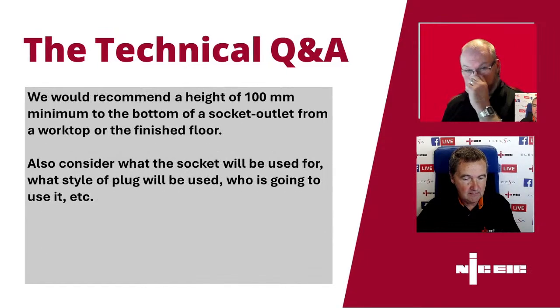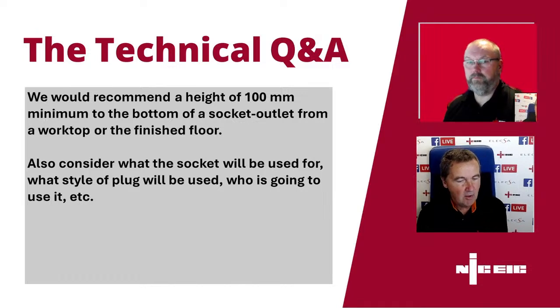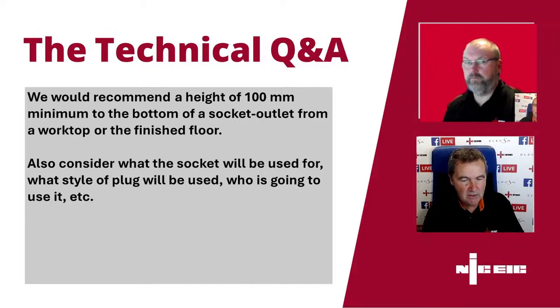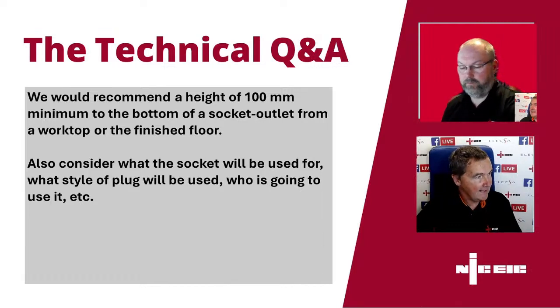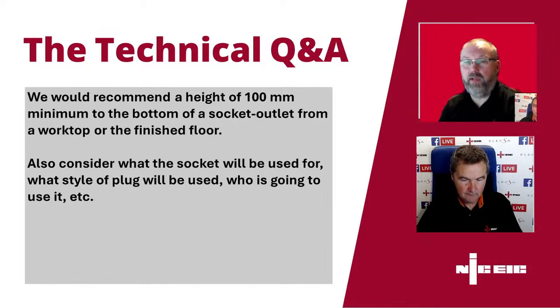We've got guidance in the Pocket Guide app, which says that we recommend a height of at least 100 millimetres from the bottom of the socket to either the worktop or the finished floor, but also consider what the socket will be used for, in particular what type of plug is going to be used in it, who's going to be using it, etc. So yeah, no specific dimension given in 7671, but it clearly has to be done so that the distance won't affect the safe operation of the socket outlet with its associated plug, and we would recommend 100 mil. Anything you'd add to that, Craig? No, I think you've covered it. Only to say it's in Pocket Guide 5. So if all of the guys have got the Pocket Guide app on their phone, reference Pocket Guide 5, and it's clearly marked in there.